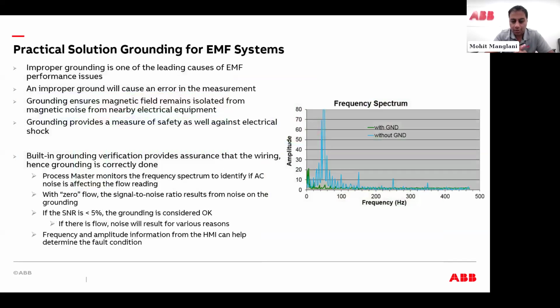Grounding. A mag meter's coils are generating a magnetic field. The magnetic field is prone to disturbance, period. The other thing with mag meters is that typically they might be using the same power panel as a drive, a motor, a bigger device, a 480 volt power supply. A mag meter is a very low power device, so it's going to pick up noise. Obviously, if you're using this for control, operation, or billing, you want to minimize noise as much as possible.